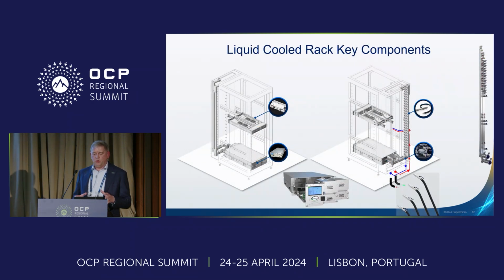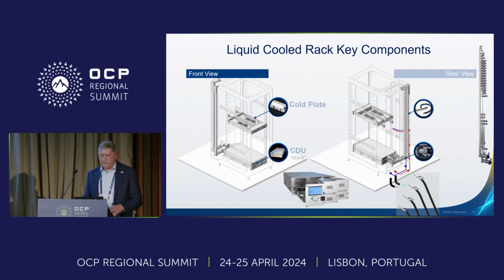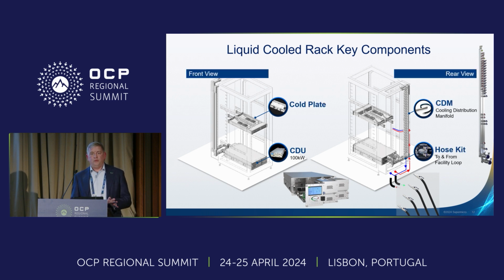Within a liquid-cooled rack we have several different components, and I'll touch on each briefly. Going clockwise, the cold plate, which I talked about, gets affixed on top of the CPUs, usually the GPUs, and occasionally the memory too. Sometimes it's not a cold plate but more like a blanket for the memory, though most of the time it's a cold plate.